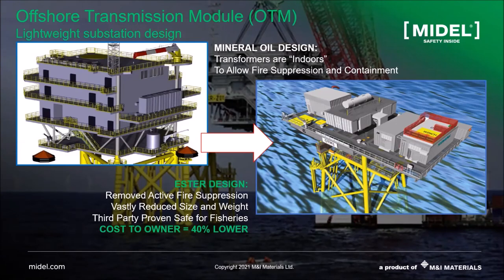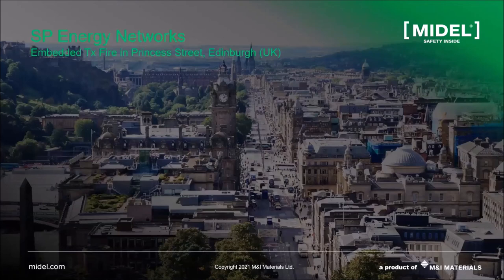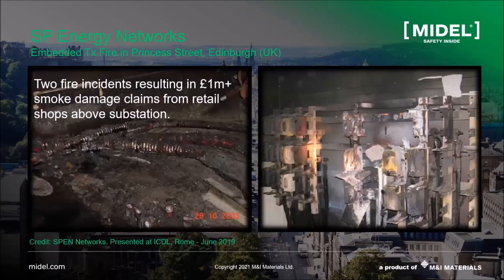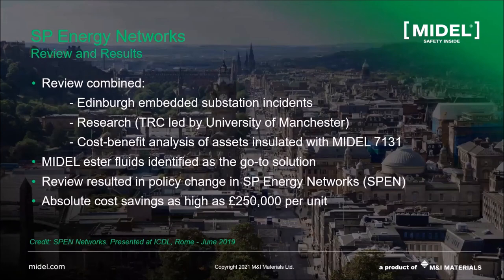Now, another innovation with substations on the next slide: you'll see Scottish Power, their energy networks. They've got a very large network underground on Princes Street, which is their high-end retail street. And the worst case happened: they had two fire incidents where transformers caught on fire and really damaged all of the business above. So business continuity was interrupted, and insurance claims were lodged, not just from the utility, but from all those businesses. They did very large research on what they should do to change all of that. And long story short, they ended up rolling out a program where they use all MIDEL 7131 synthetic esters in those underground network and radial network transformers.